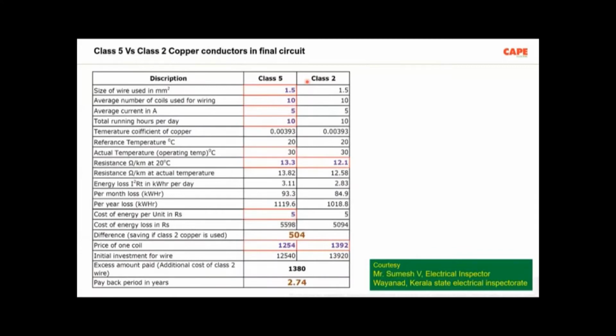Sometimes in the manufacturer's catalog, they write that the current rating of the wire is 15 amperes. But you cannot use that wire for 15 amperes always. You have to apply the derating factors depending upon the length, depending upon the filling in a conduit, and so on. So in all these cases, class 2 copper is considered, whereas in India, we always use class 5 copper conductor, which has a higher resistance.